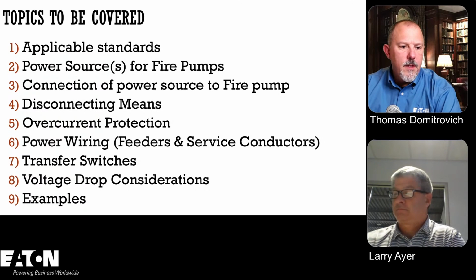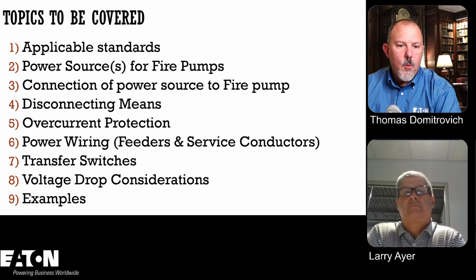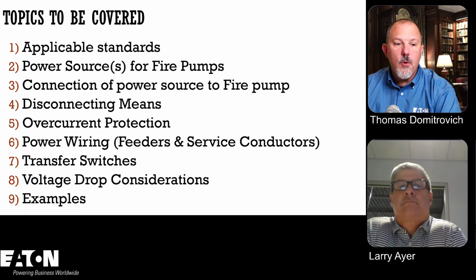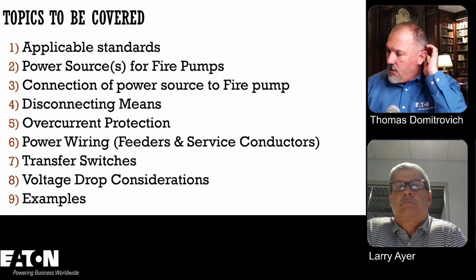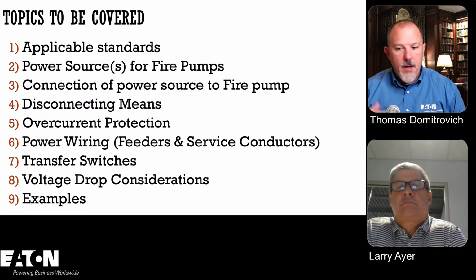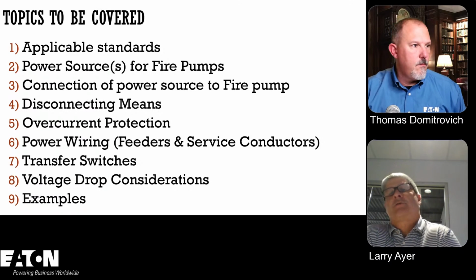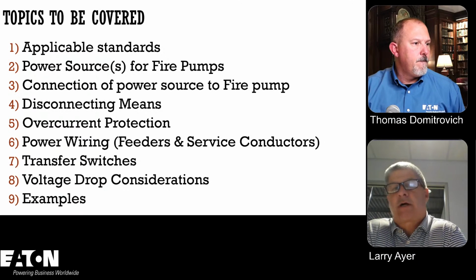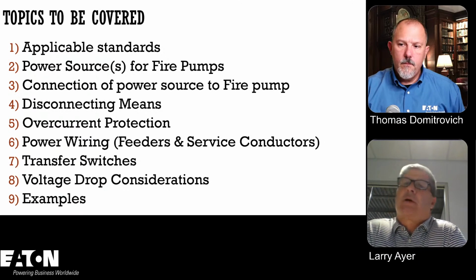Oh, installations with more than one fire pump require separate fire pump controllers, and that's a question mark. Do they require that? So can you have more than one fire pump off of one fire pump controller? Do you know that answer? I would assume that you have to have two separate ones.